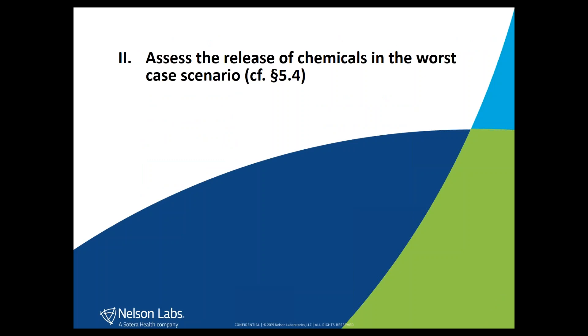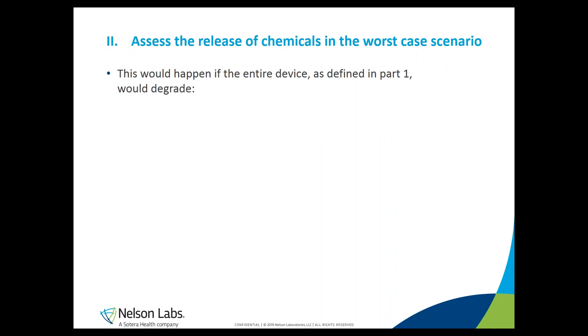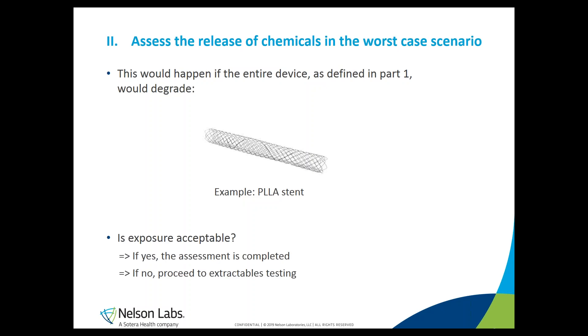In step two, you will assess the release of chemicals in the worst-case scenario, as described in paragraph 5.4 of the final draft. This will happen if the entire device as defined in part one would degrade — obviously the case for biodegradable medical devices. When we speak about the entire medical device, we refer to the bulk material, such as PLLA stent, but also potential residues from manufacturing and from terminal steps such as sterilization. If you cannot demonstrate your device will be safe, you will need to proceed to extractable testing.